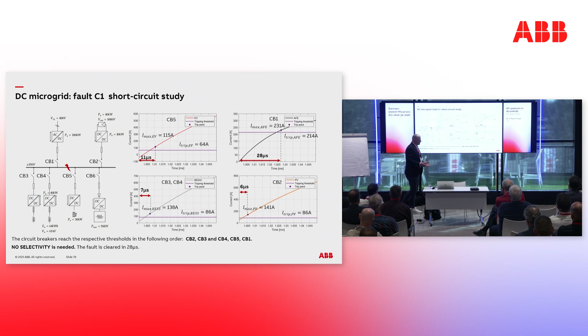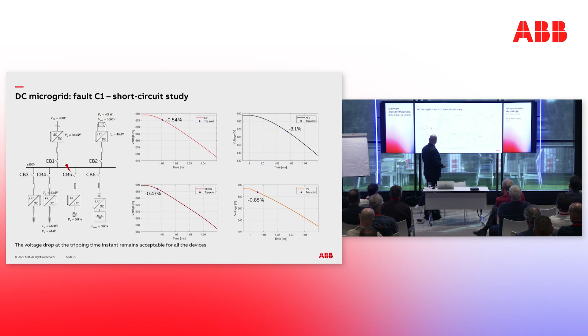Essentially, the conclusion is that all the circuit breakers will trip. This is quite a trivial case. There is no selectivity. What is a little bit more interesting is a case when we have a fault here. I had a very interesting discussion last week with a customer. Do I need a circuit breaker for the in-feed? Just for the record, they have a redundancy in the supplies and an isolated AC to DC conversion.